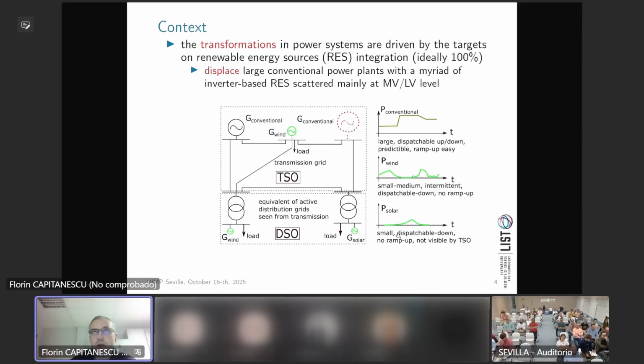Same for solar, I would say it's maybe easier overall to predict solar. Again, no ramp up. And the worst thing is that, when my main focus is controlling voltages at transmission level through reactive power dispatch, the biggest issue is that you have plenty of these distributed energy resources connected in the distribution system, and they are not visible to the TSO. So the TSO can take actions believing that it improves voltages in transmission, but that may harm distribution.